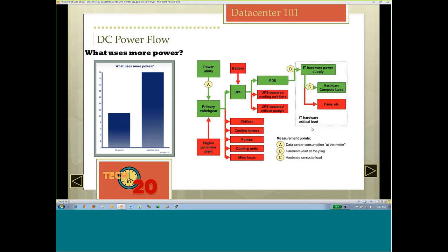They're doing some step down voltage, and that comes into a thing called switchgear. The switchgear is connected to that and the generator. So anytime you switch over, if utility power goes down or something happens, the generator comes on, that switchgear is going to define where the power's drawing from. That then flows into the UPS and also other things like chillers, cooling towers, pumps, etc.